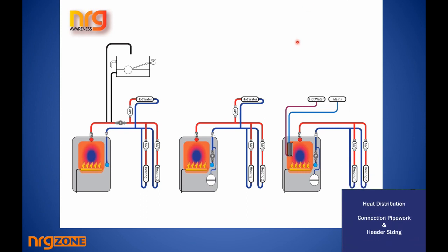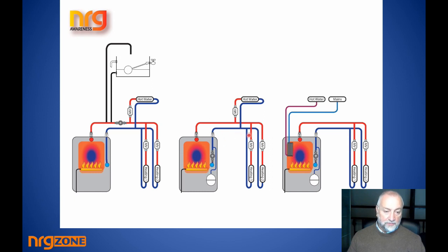Everything that I have to say will be based around this part of heating systems, that is, where a pump is either pumping from an open system going to zones, and then the fact that air should have been removed at that stage, and that we should be pumping from the neutral point, and that the pump's action, the force from the pump, should be moving towards the zones.